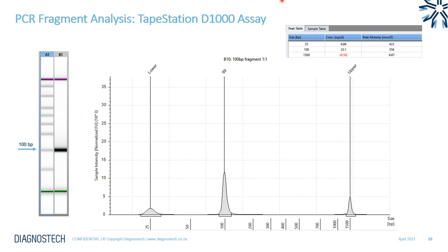The TapeStation can also be used for PCR fragment analysis — whether for amplicon QC, PCR/qPCR QC, or restriction enzyme digests — to accurately quantify and size PCR fragments. For example, a 100 bp fragment run on the D1000 assay shows on the gel image that the fragment perfectly lines up to the 100 bp ladder marker. The generated peak table identifies the three peaks detected in the assay: the lower marker, the sample fragment, and the upper marker, providing both concentration and size for each peak.